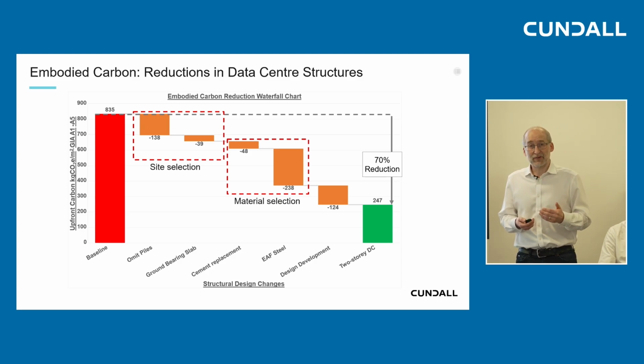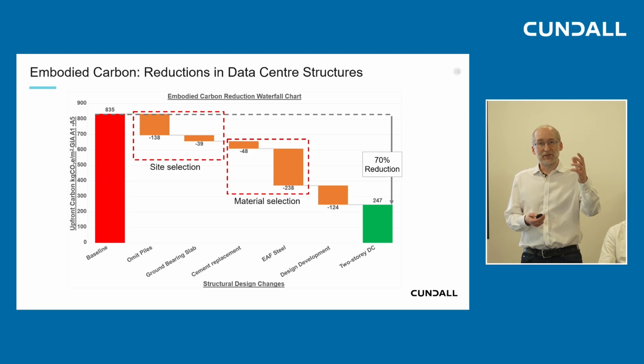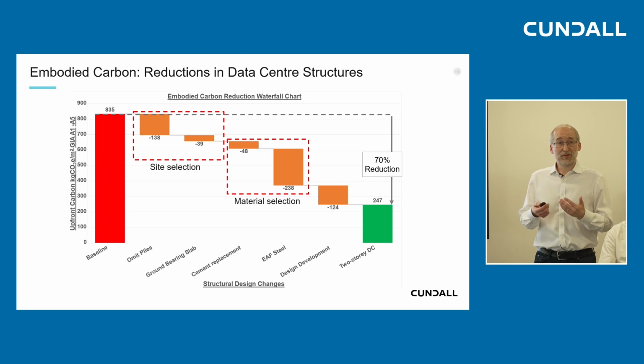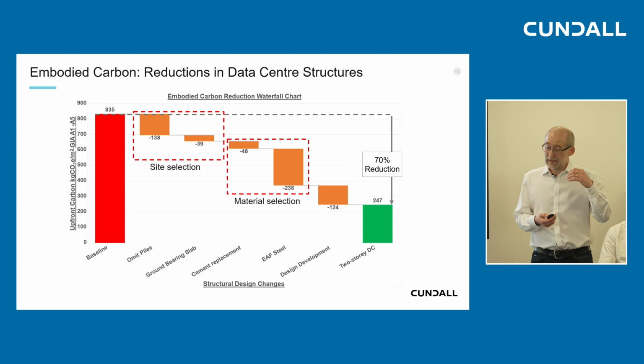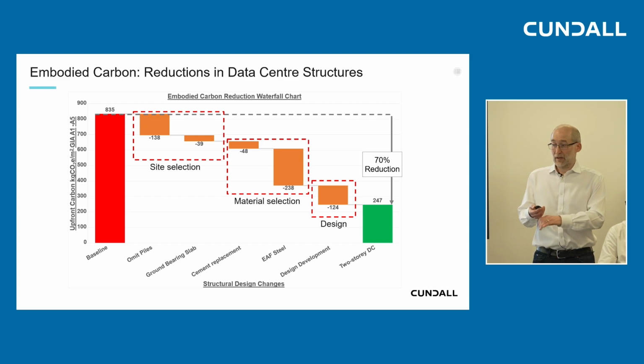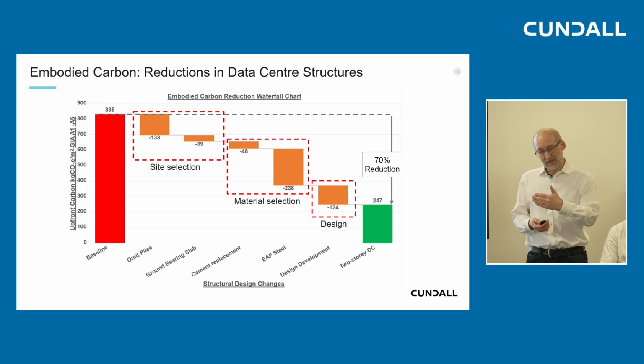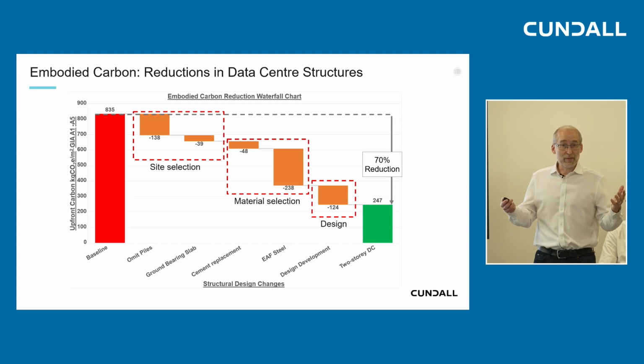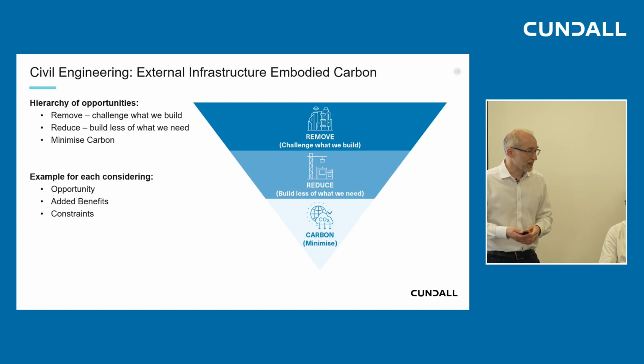The second part of it was material selection. So looking at concrete in particular, can we use cement replacements to reduce embodied carbon? And can we also look at using lower carbon steels? So this is electric arc furnace steel, which uses a much higher percentage of recycled content and uses a lower energy source. So we can get some really good reductions with the way that we select materials. And then finally, looking at design, can we get design improvements to reduce embodied carbon? So refining the design, improving the design. With this particular example, we added some columns towards the edge of the data hall, which managed to reduce the span of the structure quite a lot, and that made quite a big difference. So overall, we managed to achieve a 70% reduction in embodied carbon. So a great story. So I'll hand over to Damien to talk about civil engineering aspects.